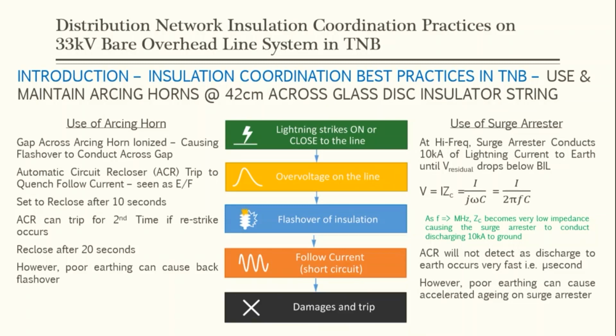So the automatic circuit recloser will trip to quench the follow current, and the recloser will be set to reclose at 10 seconds. The ACR, the automatic circuit recloser, can trip for the second time if a restrike occurs across the gap. So it will reclose after another 20 seconds, from the dead time to the reclaim time. However, with poor earthing, it can cause back flashover.